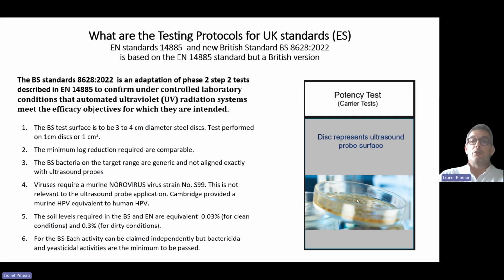Apart from what we called harmonized standard, that means the standard used to demonstrate compliance with the essential requirement of the medical device regulation, some countries like the UK have developed specific standards for UVC disinfection process. Even if this standard was developed very recently and has no direct impact on the CE mark, it's appropriate to ask whether the Chronos meets the requirement of this new standard or not.